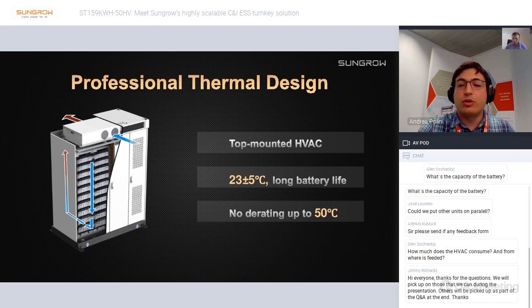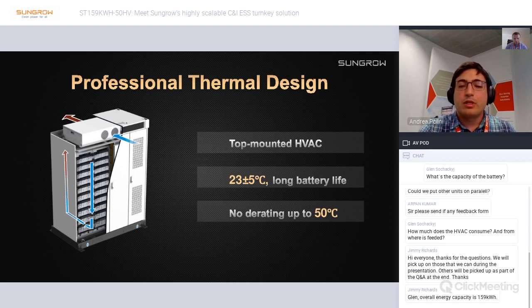The system is designed to control the interior temperature of the battery cells around 23 degrees with a variation of 5 degrees both sides, in order to be always in the best performance range of the battery for maximum power charge and discharge at all times. The HVAC can ensure nominal operation until 50 degrees C of the ambient temperature, which means that until the environment reaches 50 degrees C, the product has no derating and can operate at nominal power. So this is an advantage that you cannot have if you don't buy a full all-in-one system solution, just like the one we are proposing now.